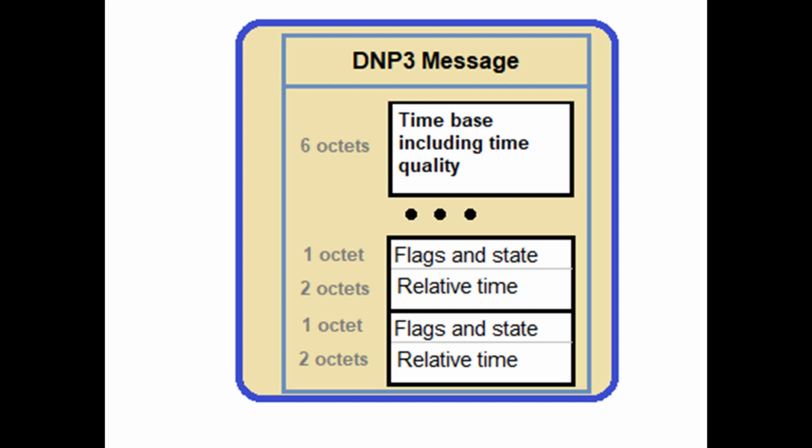Regardless of the time format used, DNP3 requires that all times be sent as UTC. However, it may be possible that some implementations violate this rule and use local time. If important, it is a good idea to check with the device manufacturer.